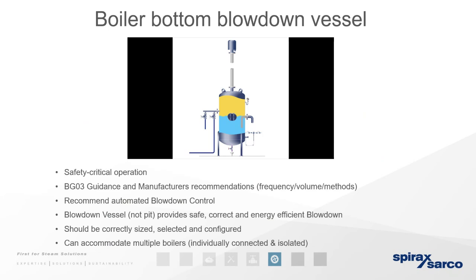So these should be correctly sized. Again, you know how much blowdown is coming from your boiler, but if you've got 4 boilers blowing down at the same rate, you will need a bigger vessel to be able to take all that before it cools down and is then able to be released to drain. It can accommodate multiple boilers, as it says there, individually connected and isolated. What that means is that on this manifold here entering into the blowdown vessel, there is a separate pipe for every boiler or everything that's blowing down.